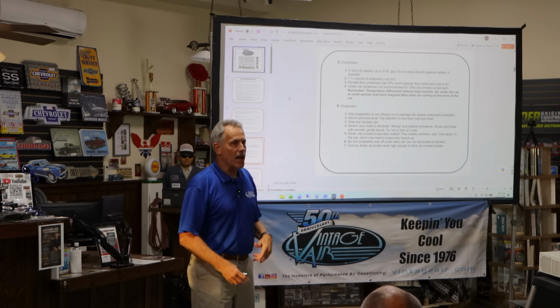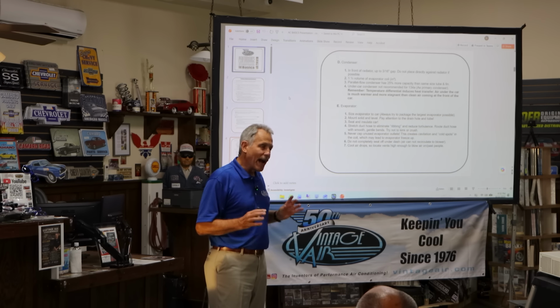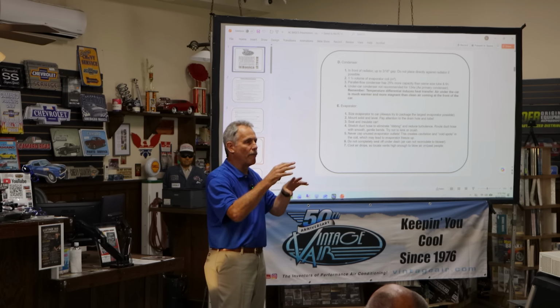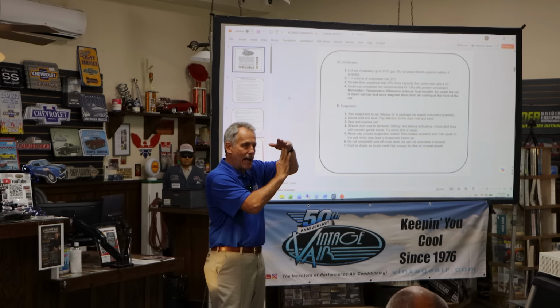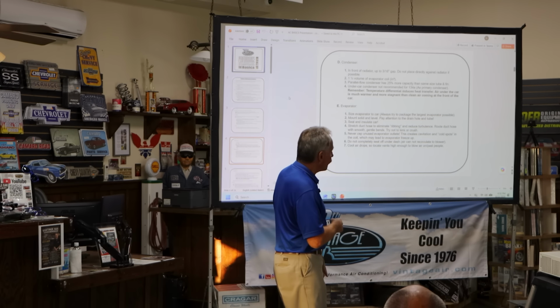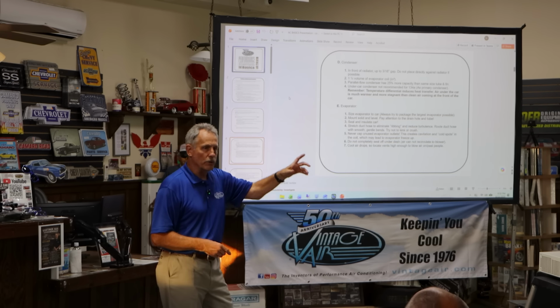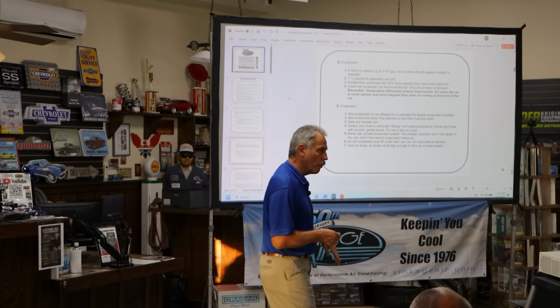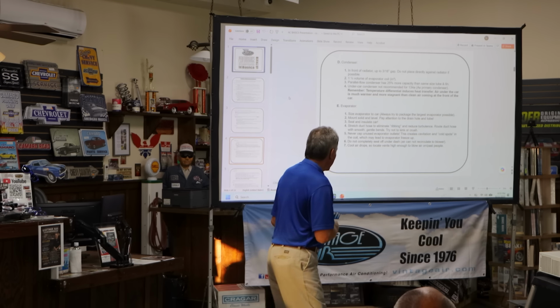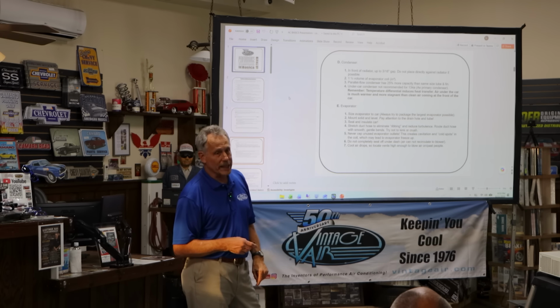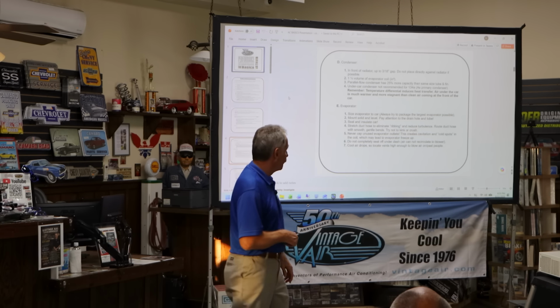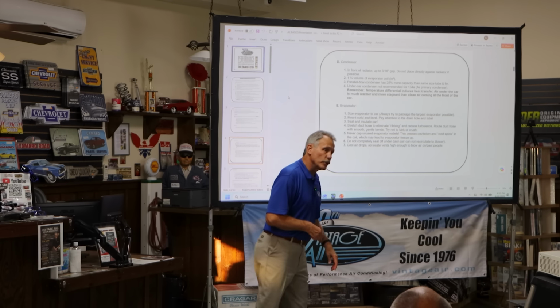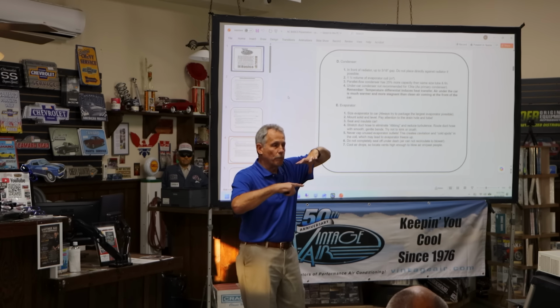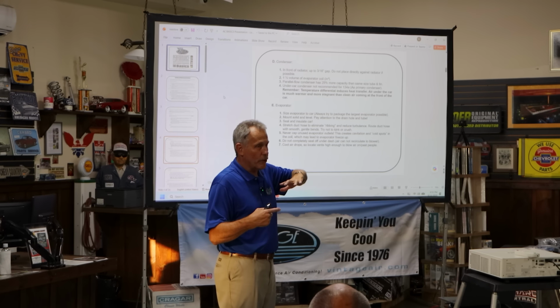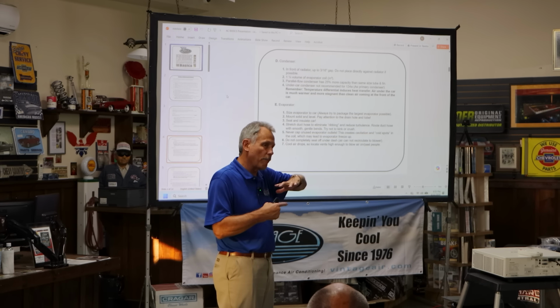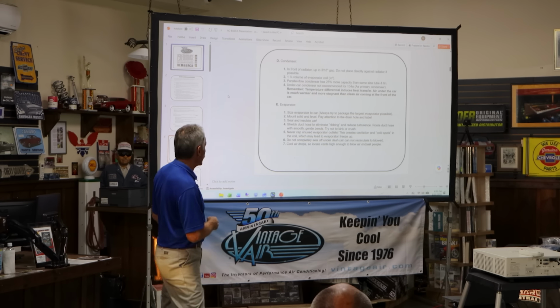You've got a case that's designed for proper airflow with all 3 of those vents open. By capping one, they reduced the airflow through all of them because of the turbulence created where the air was trying to get out. So if you're not going to use every outlet on a system, just take a piece of duct hose and dump it on your feet or something like that so that you get good airflow out of all those outlets. They're set up to work together when they're all hooked up. And the other thing that'll do, depending on which one you plug, if it's where the probe is for the thermostat or for the ECU measuring coil temperature, you get an improper measurement there. So that's the other reason not to do it.